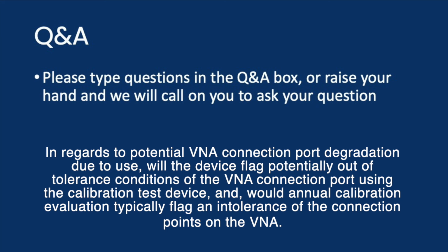And if there's any deviation there, then you know that something is wrong, and you can just at that point think about inspecting that open connector if it's been dropped one time too many off a tabletop, or examining either your cables or your connector on the instrument.